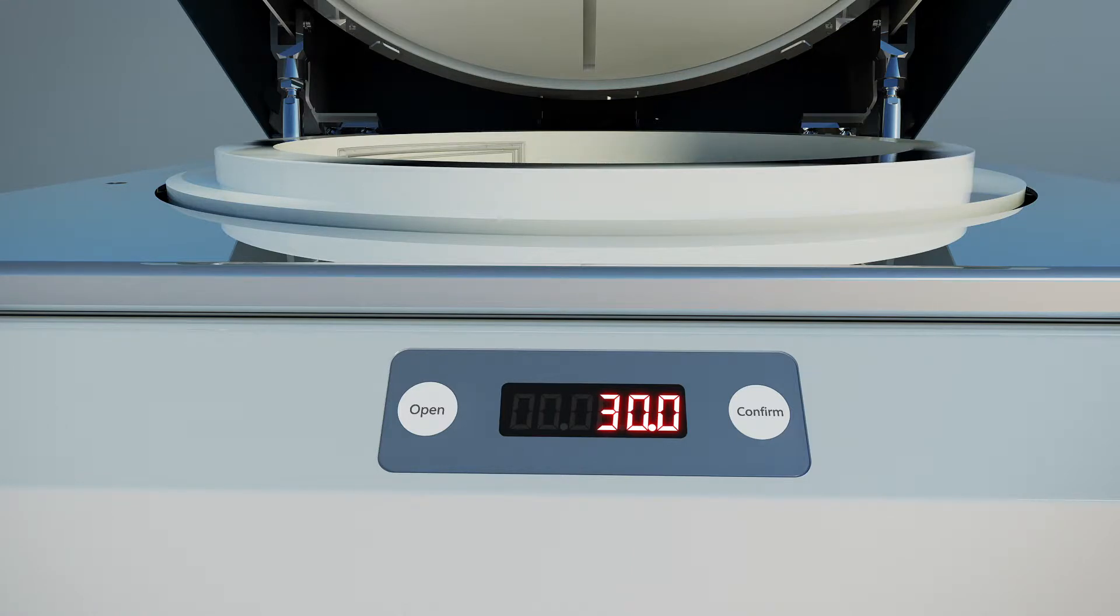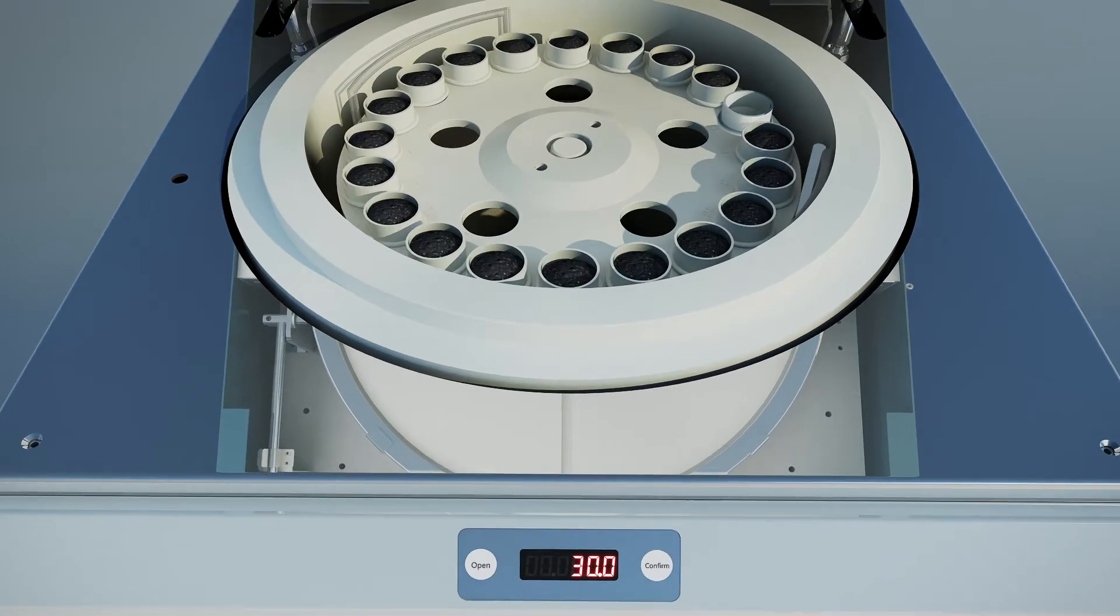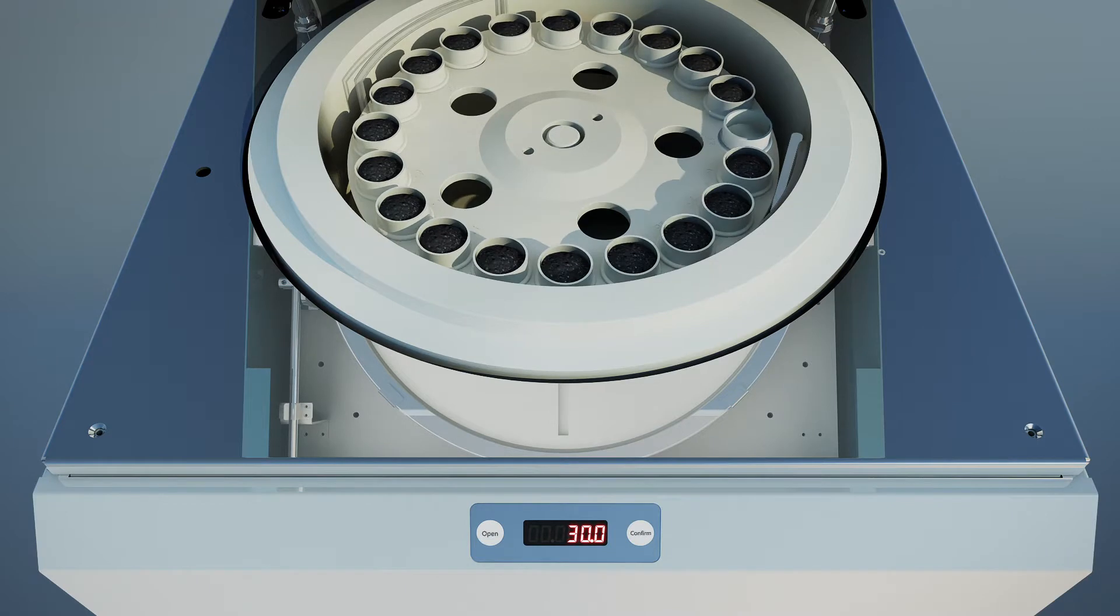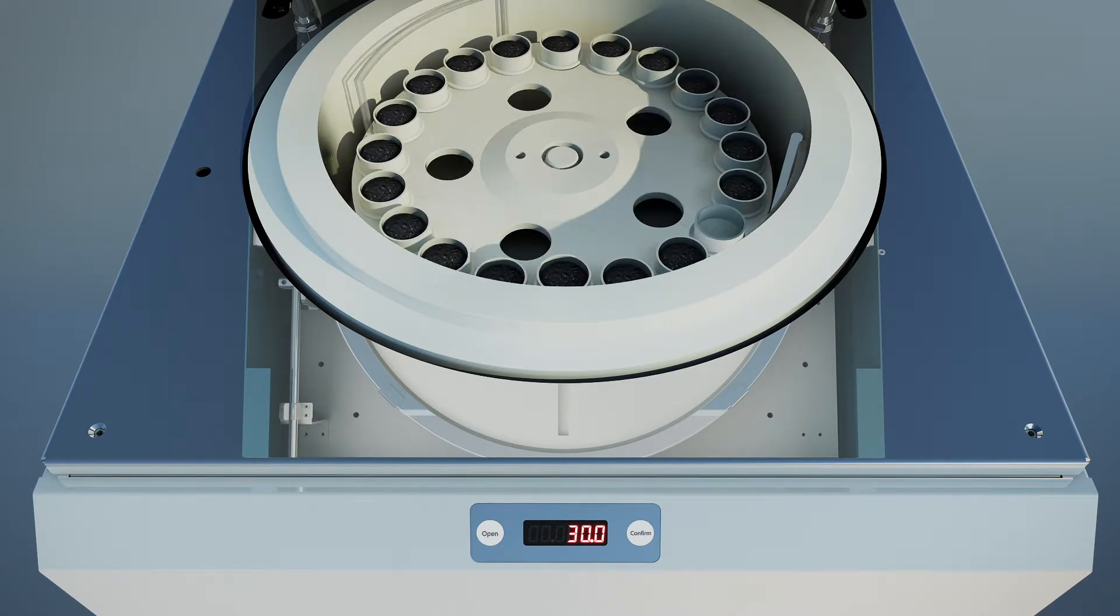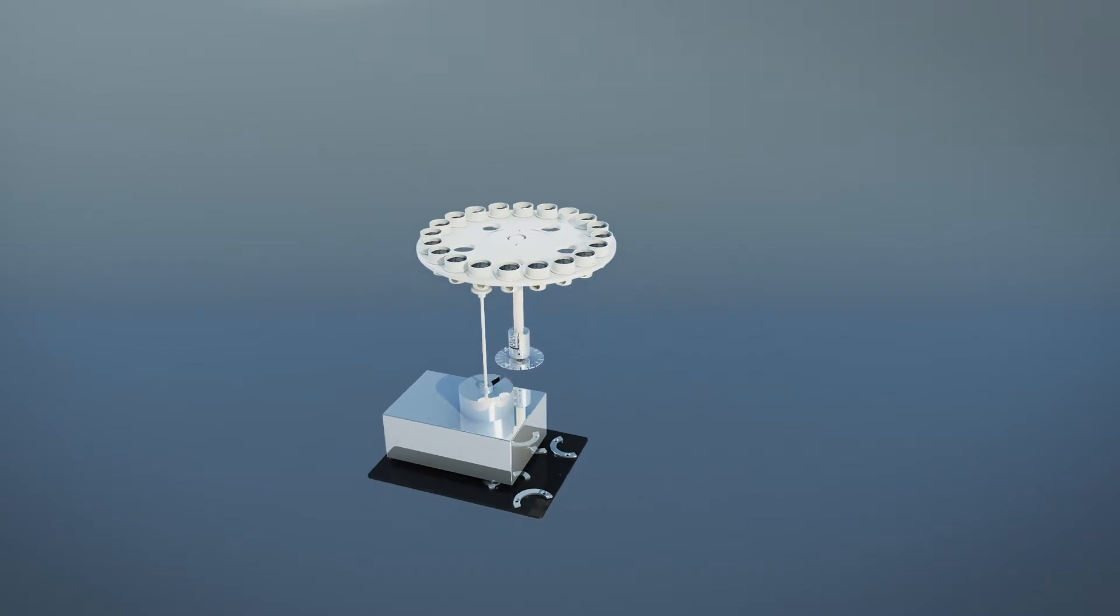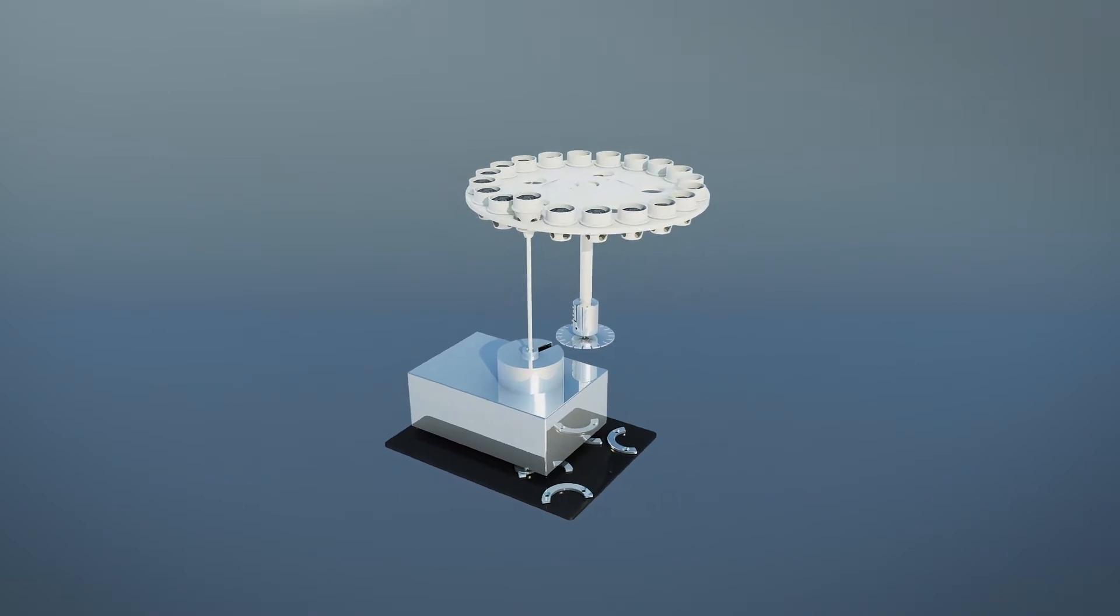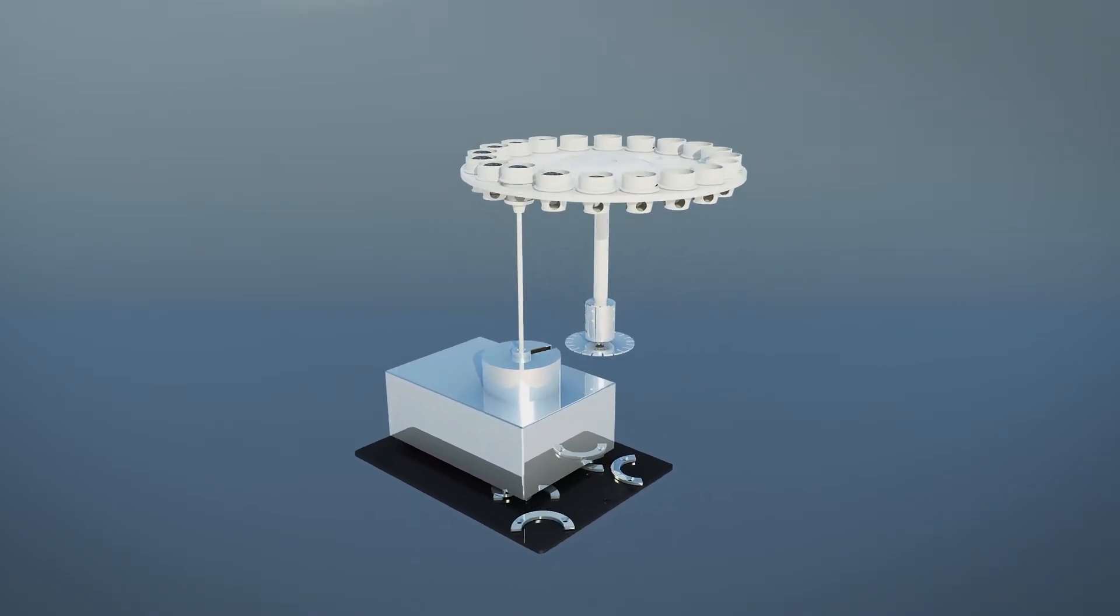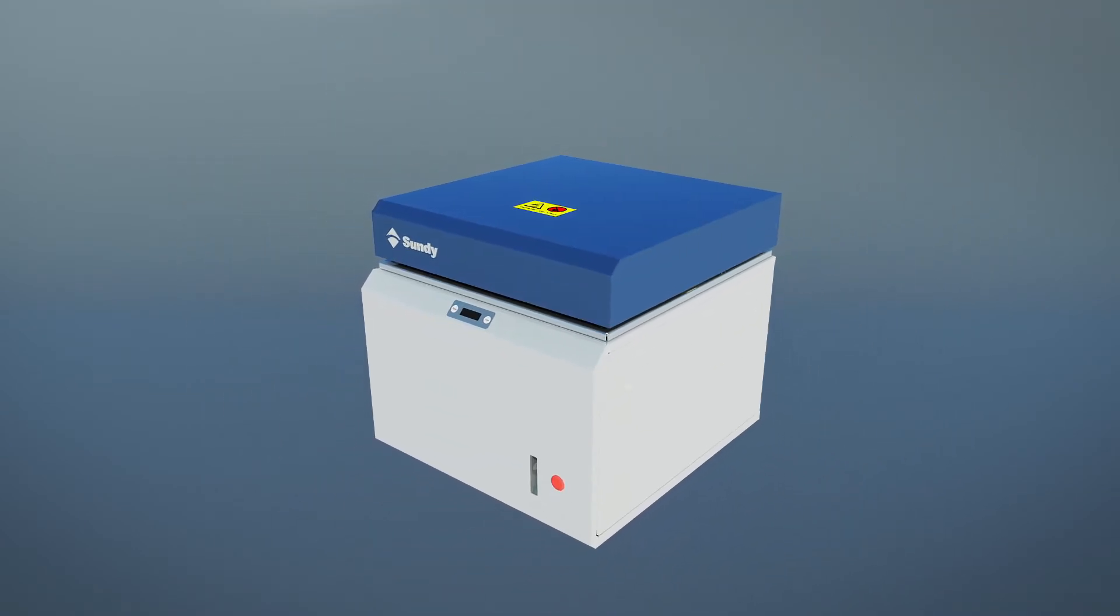In addition, the front of the analyzer is equipped with an external display of the analytical balance, which can display the balance data in real-time, convenient for sample weighing and improving working efficiency. The internal analytical balance is equipped with automatic correction function to ensure each weighing result is accurate and reliable. It meets ASTM and ISO standards.